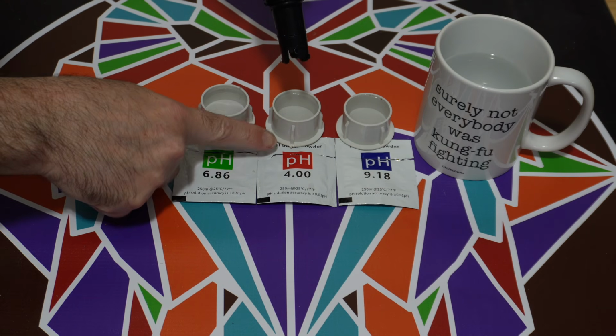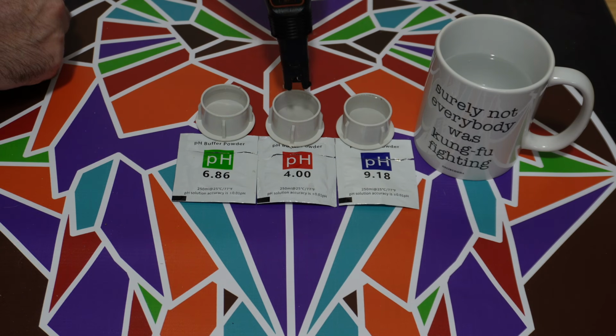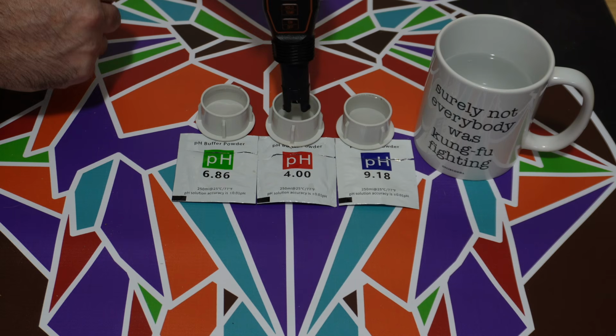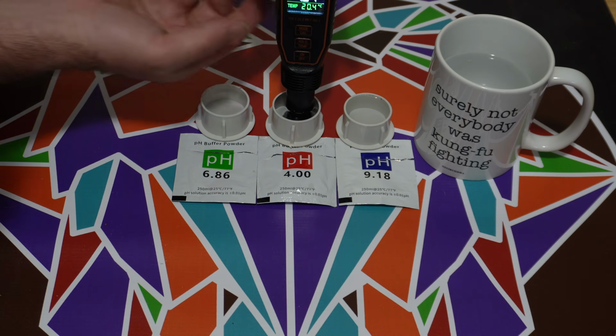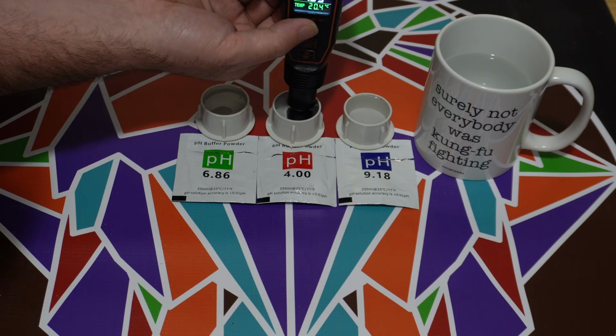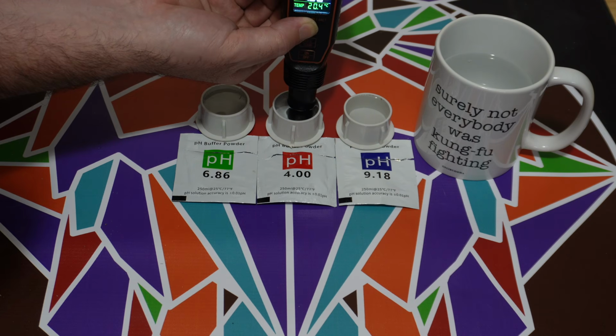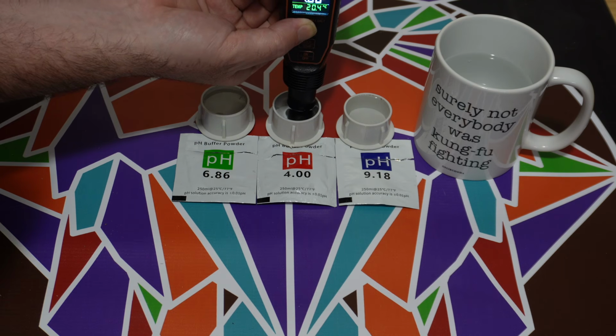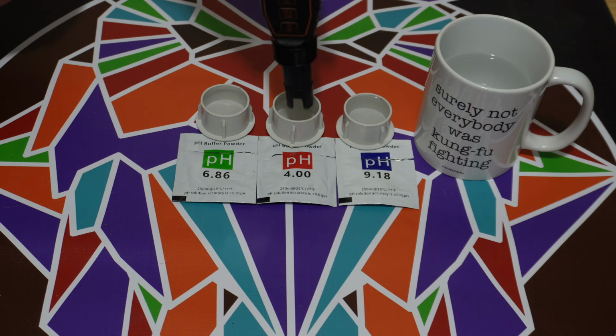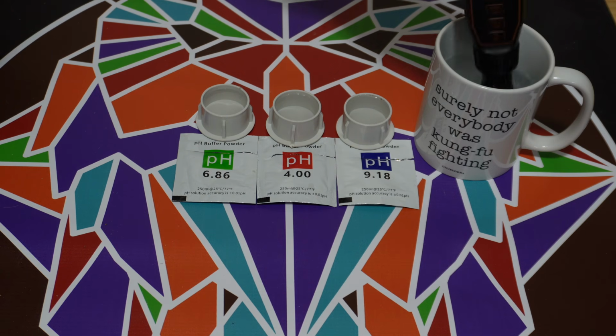Next up, we're going to go into the pH 4.0. So let's dip this in here. And again, we're going to come up here. We're going to press the mode calibration button, hold it for about 6 seconds until it flashes 4.0. There it goes. And actually, we're going to hold the button down until it stops flashing. There we go. Okay, it stopped flashing. I can let go. We take this out, we rinse, and we repeat.